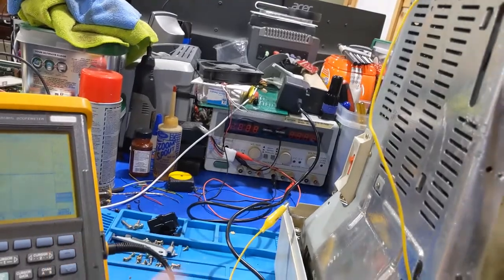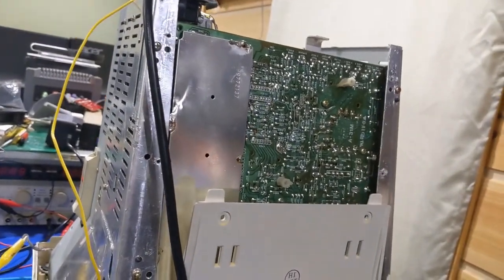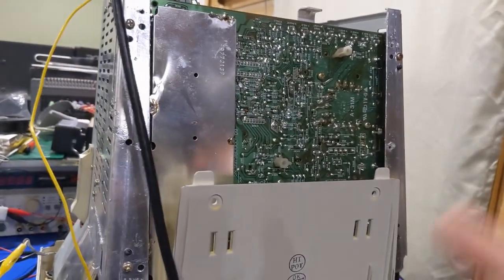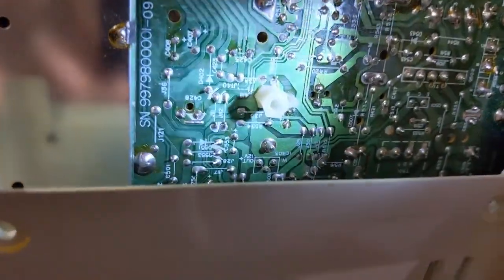So that voltage should be significantly higher than what it is. We were only getting about 30 to 40 volts peak to peak on the drive output waveform going to the yoke. That's not high enough. So there's clearly a fault in this circuit, obviously - we need to find out where that fault is.